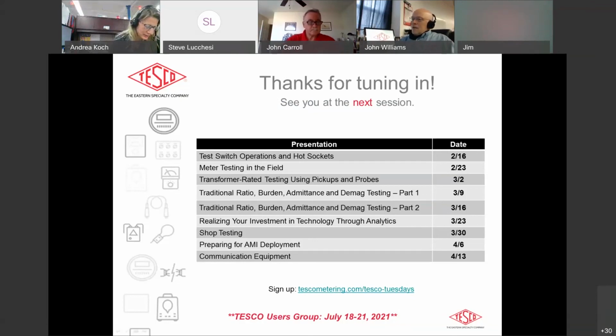Yeah. And if you have the wrong factor in there, if you have two CTs in an installation at one ratio, and the third was put in because it had a problem and somebody replaced it with the wrong ratio, and now you're metering one of the three phases at one ratio and the other two at another ratio, and God knows what the factor is in the meter to accomplish that. So there's a lot of things that go into transformer rated installations, as we all know, and some of those headaches can be gotten rid of by using the self-contained. Yeah, that would maybe be a future presentation, Andy. Make a note of that one.